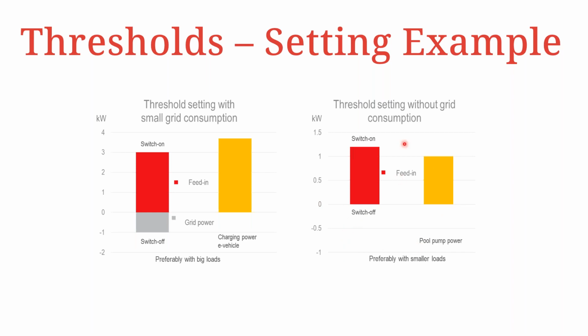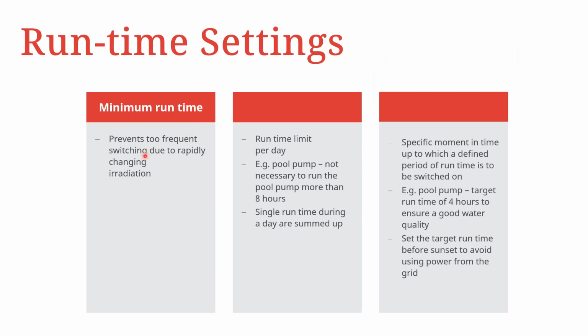When it comes to the runtimes, like I said, you have to define the minimum runtime, so it prevents too many on and off operations of the load. Then the maximum runtime, which is the runtime limit per day. If it's something like a pool pump, there is no need to operate it for more than 8 hours per day. So here you have to decide how many hours of operation, for instance for a pool pump, would be enough to turn over the entire volume of the pool so that all of it is filtered and cleaned. In addition, if the pump has been operating several times on and off, maybe 20 minutes on, 30 minutes on, and so forth, those would be added up toward the required runtime limit per day. And then what is the target runtime?